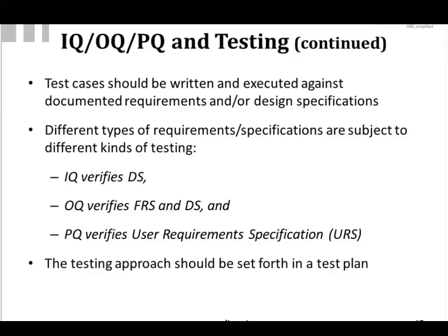And you should have those results available. You should have at least some kind of statement from a vendor. If it's a contract set of resources, you want to make sure you have some kind of output to show it was done. And the same for IQ. If your vendor is doing your IQ, you want to make sure you have a copy of the results.